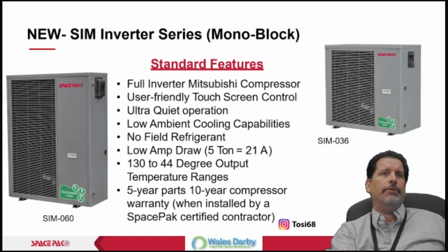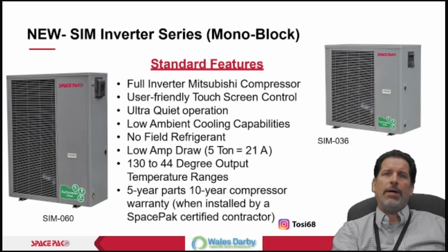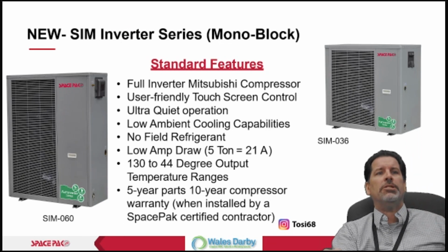Here's the SIM, right? Inverter. What is it? No field refrigerant. You're not putting any refrigerant in the homes, right? 5-year parts, 10-year compressor. That's what our SpacePak certified installers, registering our equipment, what we do. I mean, this thing can be, I don't know, hundreds of feet away from the home, right? We can dig a trench. We can put some insulated pipe, let's call it Uponor, EcoFlex or something. We can have this behind a barn, behind the garage, somewhere out in the meadow if you wanted to, just away from the house. Some people aesthetically, they don't want to see things. So this is a perfect scenario. With water, we can have longer distance, more control, less loss, right?